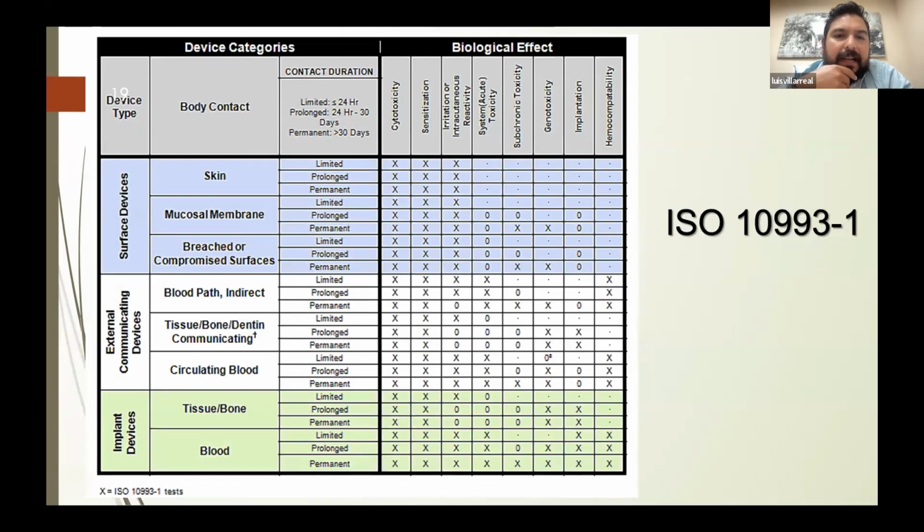For this kind of system, we looked at the international norms to see what kind of studies I had to do for this medical device. We are talking about a mucosal membrane, and the idea is that this membrane is used only 8 hours, so it's a limited contact duration.